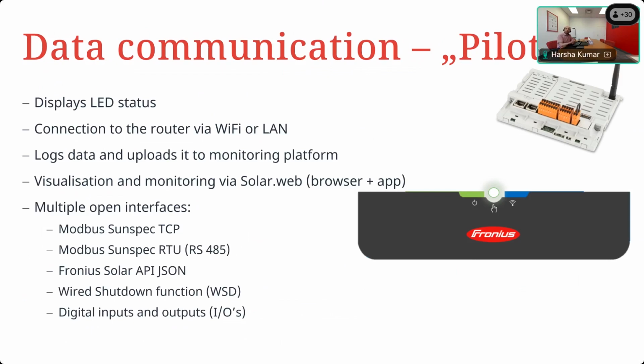There is no more AB switch on the data manager, like on the previous Gen24 data managers. In addition, you can still have all the other interfaces we had on the data manager: Modbus TCP or Modbus RTU, the API, the SolarWeb API, the push service, the wired shutdown, and digital IOs. The only thing missing is the dry contact that was on the previous model of inverter for rapid shutdown initiation—that dry contact is missing here. Since it's missing, we'll need to mimic what the dry contact does by using an external e-stop or push stop button if you want string level shutdown.